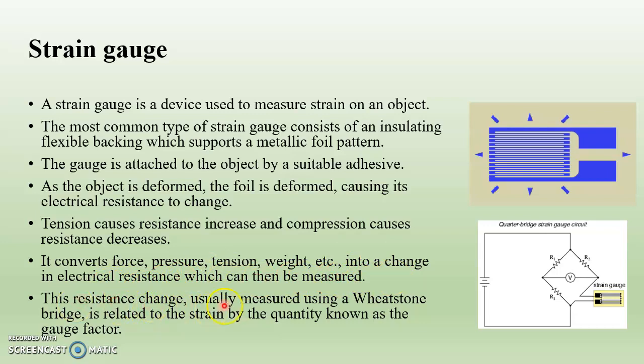This resistance change is usually measured using a Wheatstone bridge, related to strain by the quantity known as the gauge factor. This is a quarter bridge strain gauge circuit: R1, R2, R3 are the three resistances, and the fourth resistance is the strain gauge itself, which is basically an electrical resistance changing device.